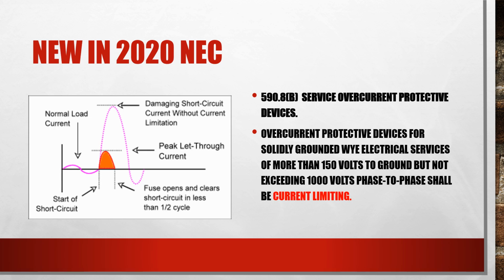Now, right here in 590.8(B), another new part of this whole 590.8, it's talking about service overcurrent protective devices. So this is where the service comes in. It says overcurrent protective devices for solidly grounded wye electrical services of more than 150 volts to ground but not exceeding 1,000 volts phase to phase shall be of the current limiting type, meaning that the overcurrent device has to be a current limiting device.